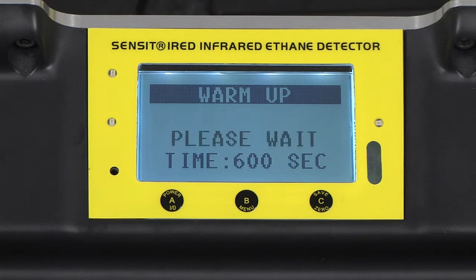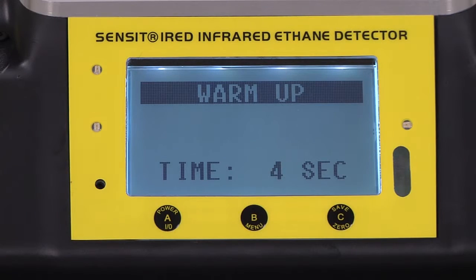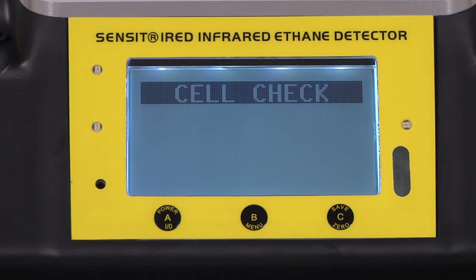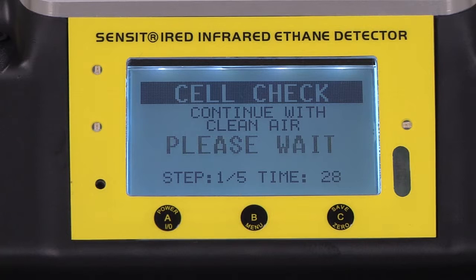And finally, a warm-up. Once the IRED has reached an optimal temperature, the countdown timer will begin from 600 seconds. After the warm-up, there will be a self-test of the internal cell. This process should take approximately 3 to 5 minutes. After the cell check is successful, the instrument will advance to the work display.